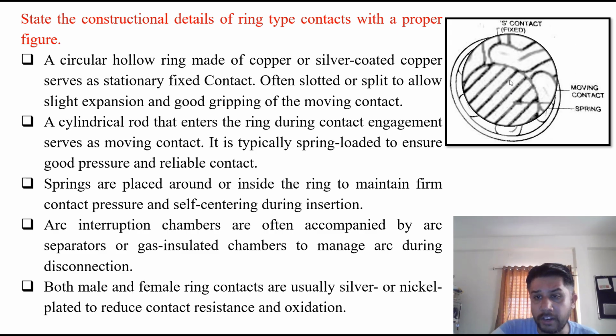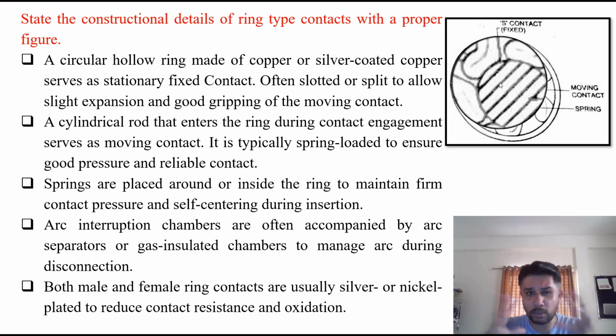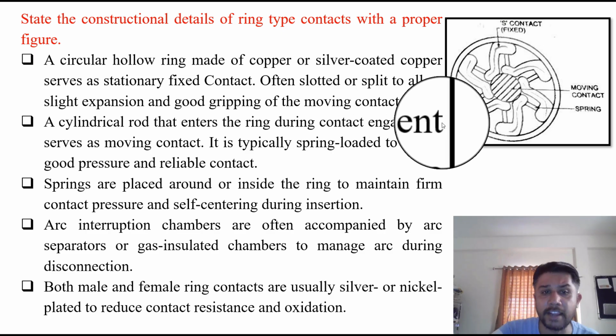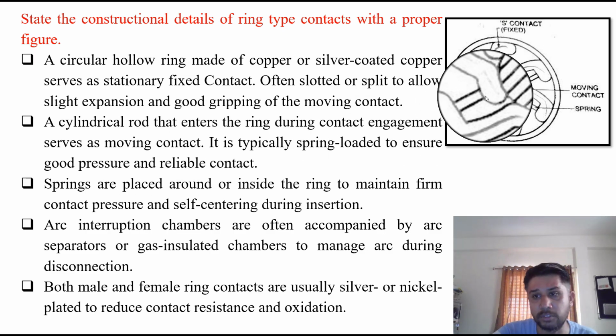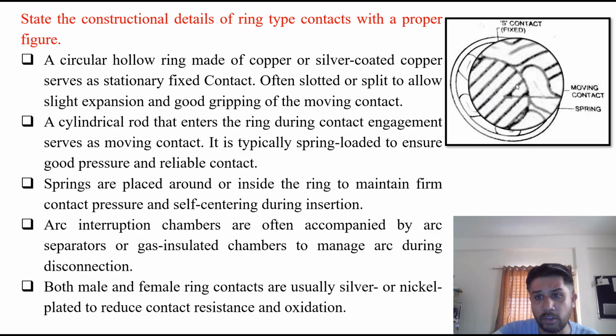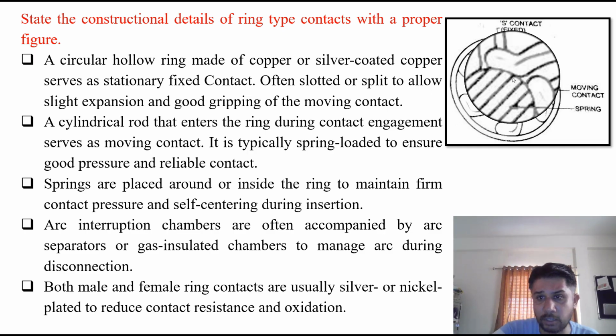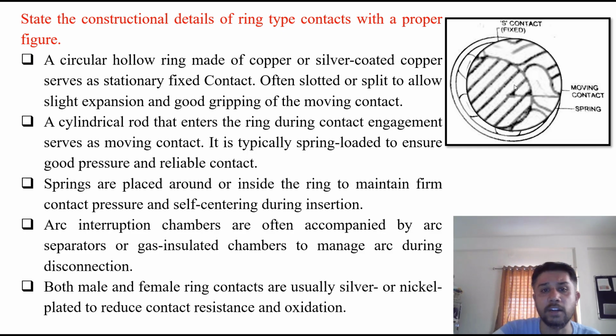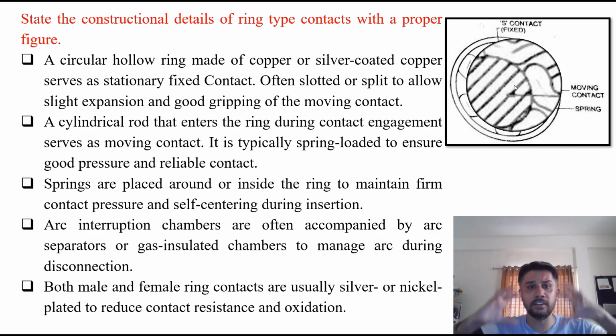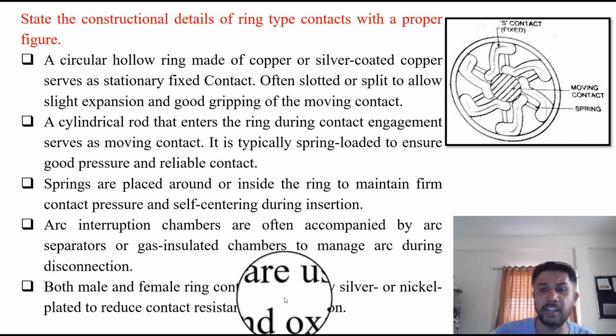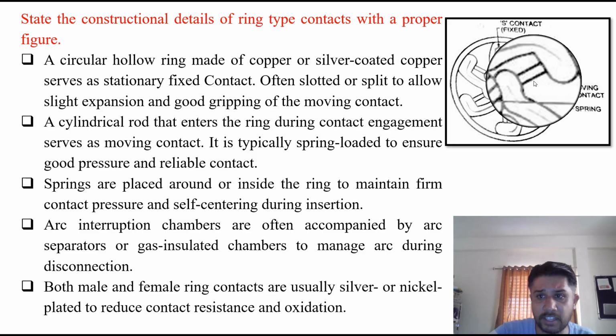This is a moving contact in between, which allows good gripping. A cylindrical rod that enters the ring during contact engagement serves as a moving contact. You can see this circular, cylindrical contact enters the ring due to the engagement. It serves as a moving contact. It is typically spring loaded. These are the springs, you can visualize this. These are the springs at the end.